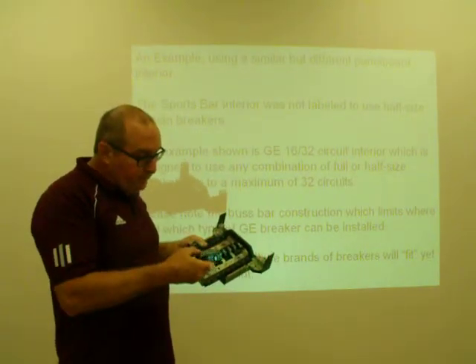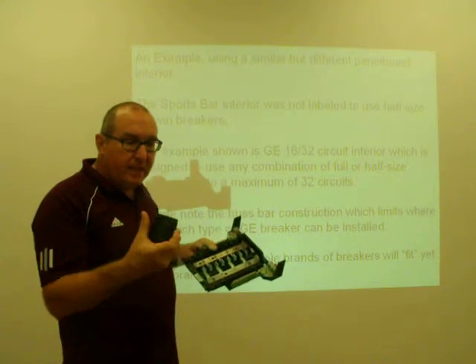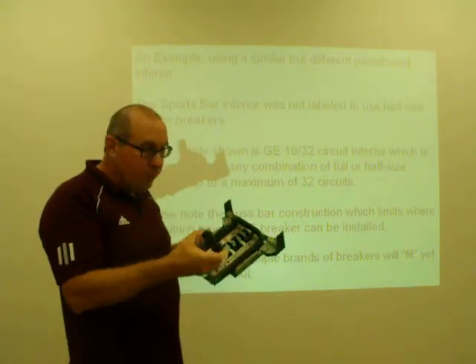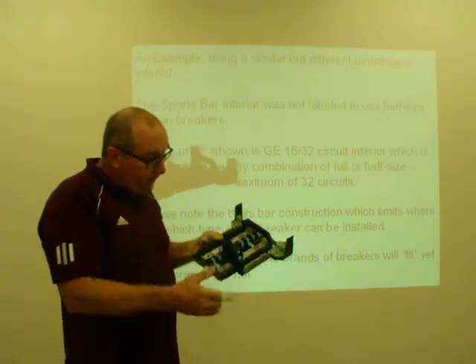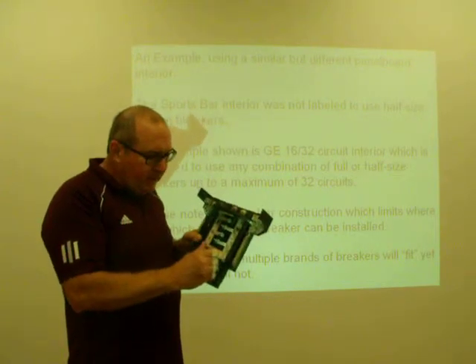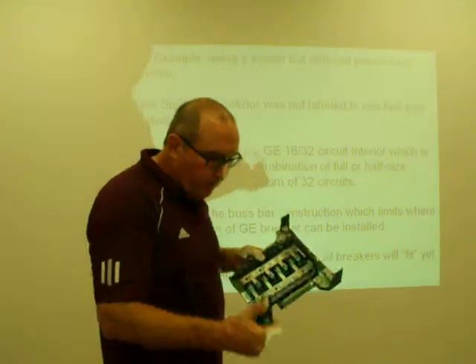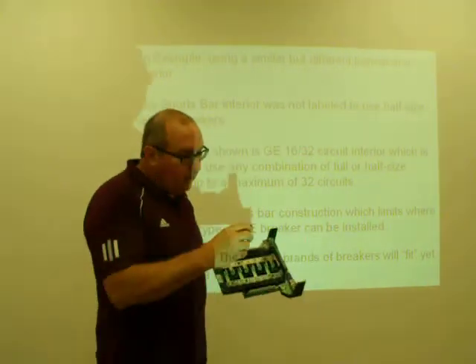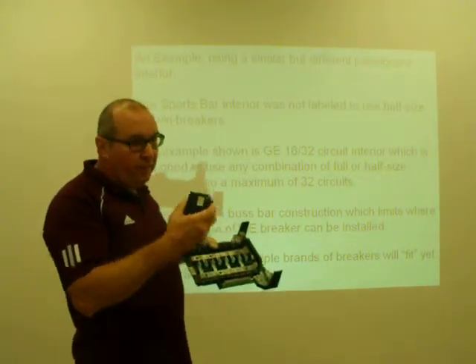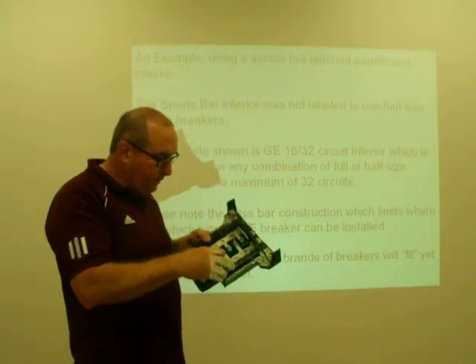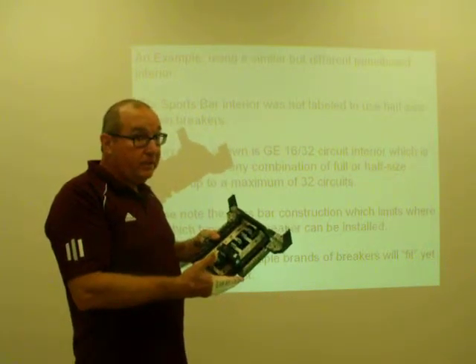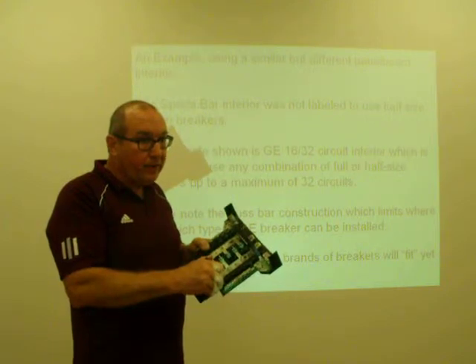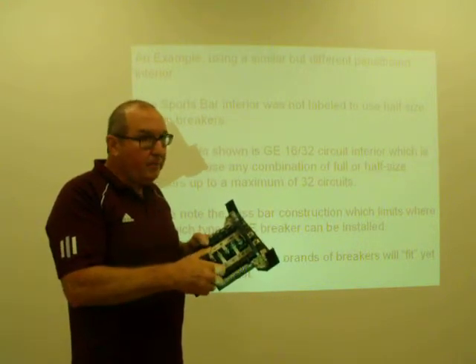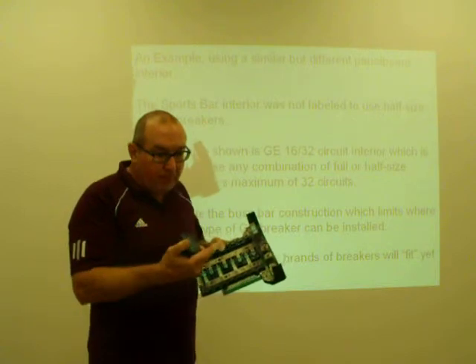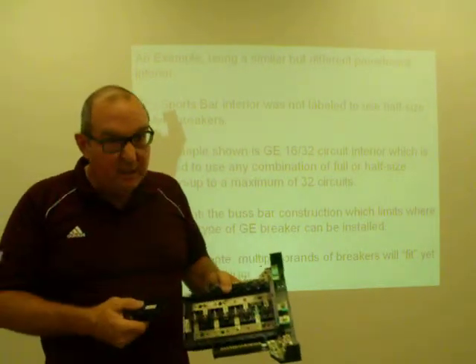This is an oddball breaker. There's actually nothing on this breaker whatsoever to indicate who made this breaker, what company, and yet it will fit. Fortunately, it seems like the handle doesn't really work very well, so I'm not even sure that breaker works. And this is an American Switch Company breaker, another company that may be out of business. It physically fits. So 3 out of the 4 breakers I've tried here, all 4 not made by GE, will fit this panel board. And most likely they would fit any other GE panel board as well.